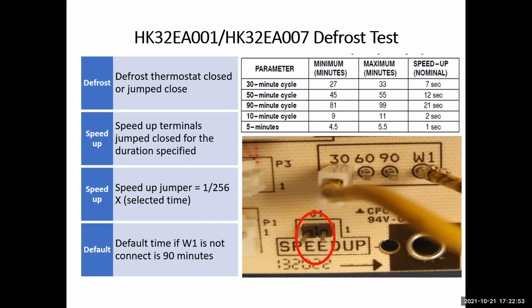Because the defrost sensor is a simple switch, it opens at a design temperature set point and closes at a lower temperature set point. The temperature can be temporarily bypassed with a jumper for testing purposes. When jumpering out the defrost sensor, use an ohm meter to indicate whether the sensor is open or closed. Along with the ohm meter, use a thermocouple type K sensor mounted on the liquid line near the sensor to measure the make and break point of the contacts. In warmer weather, not above 65 degrees, you can disconnect the condenser fan motor to simulate a colder temperature.